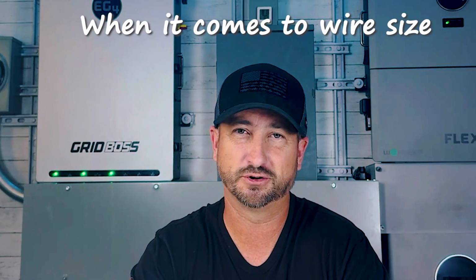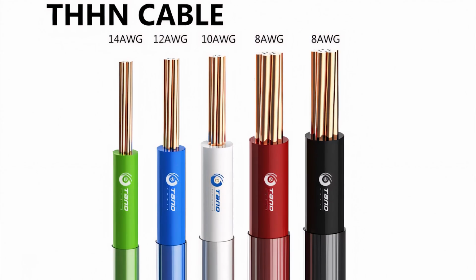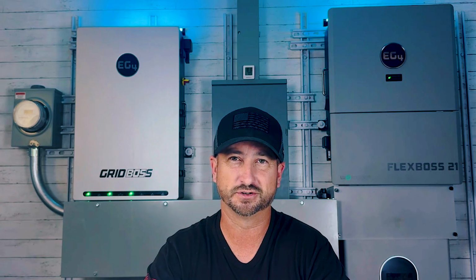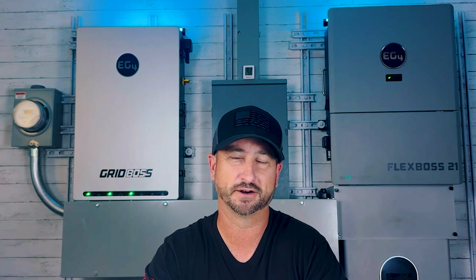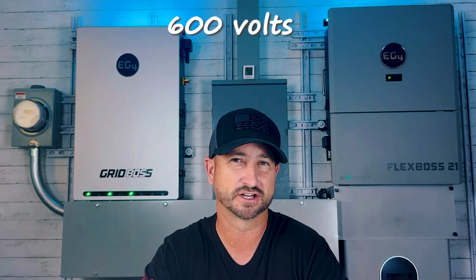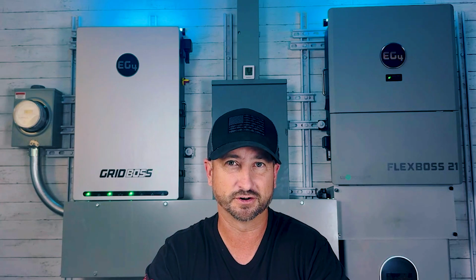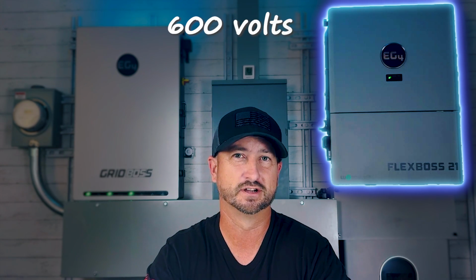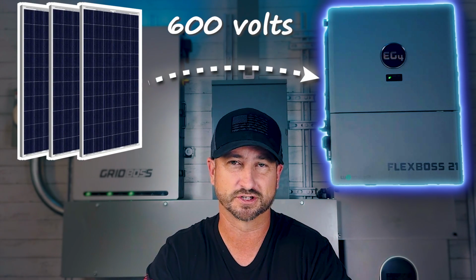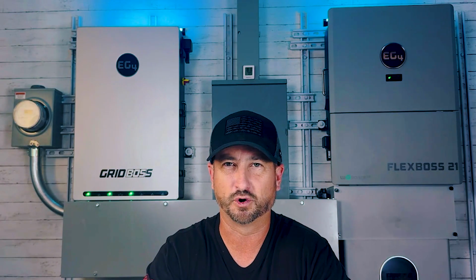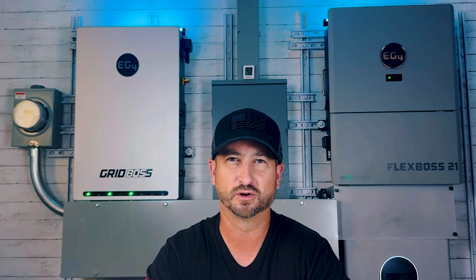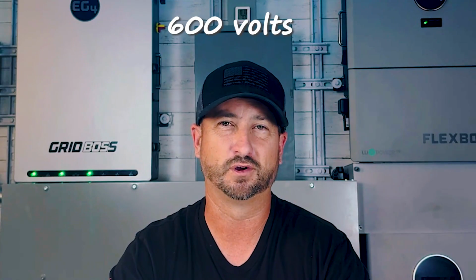It's pretty hard to get the volts side of things wrong when wiring your solar panels back to your inverter or batteries, because THWN stranded wire, which a lot of us use for long runs from the panels to the inverter, is rated for 600 volts. Some inverters now, like the EG4 FlexBoss 21 behind me, can handle up to 600 volts from the solar panels to the charge controllers. The 2-aught and 4-aught battery cables used on these 48 volt whole-home systems can also typically handle up to 600 volts. So again, volts are really not an issue.